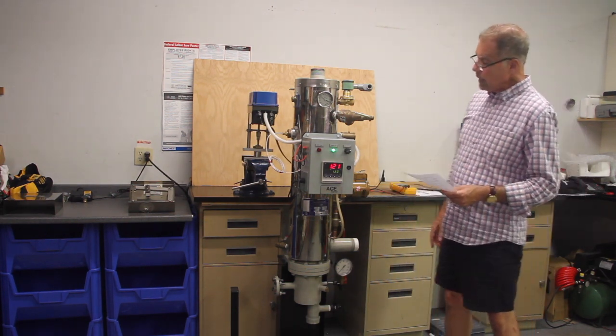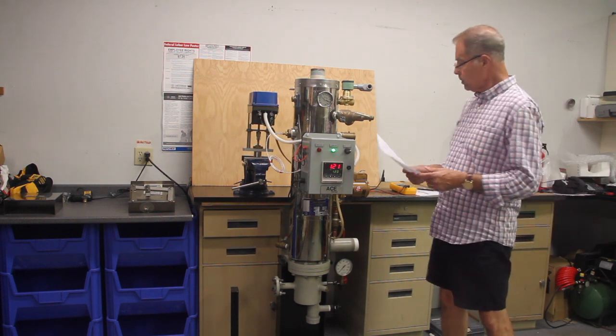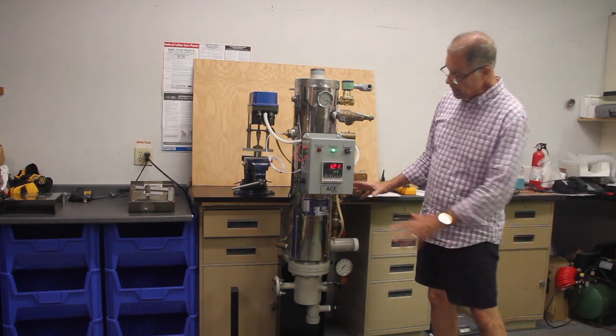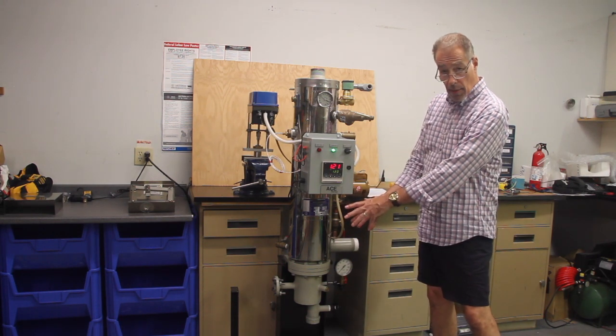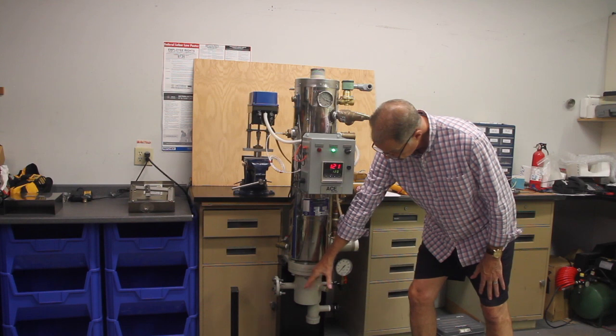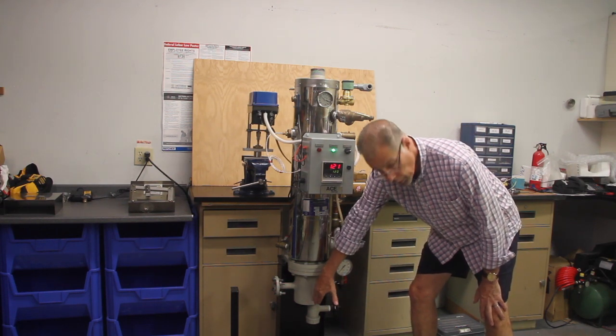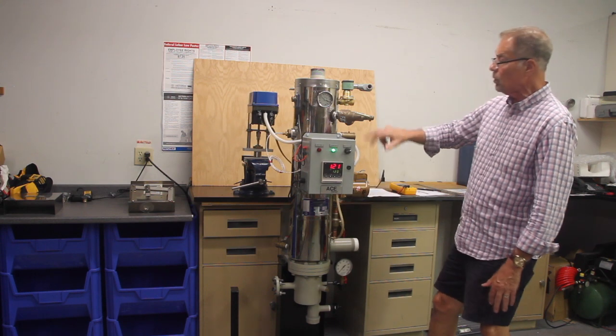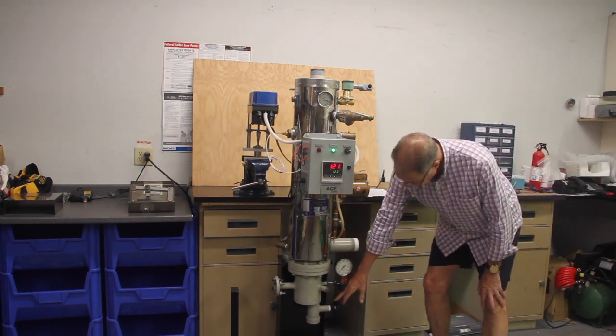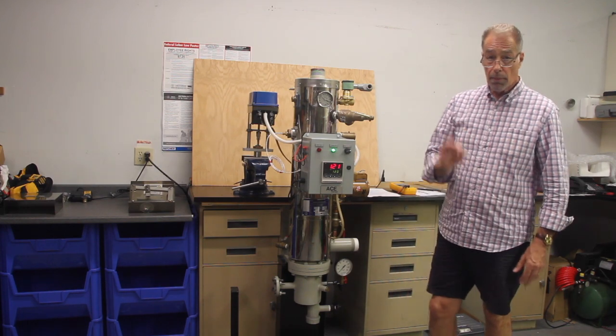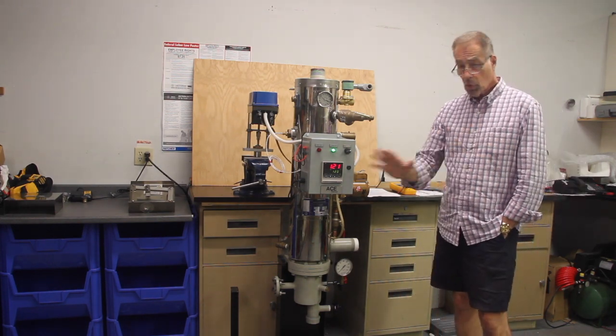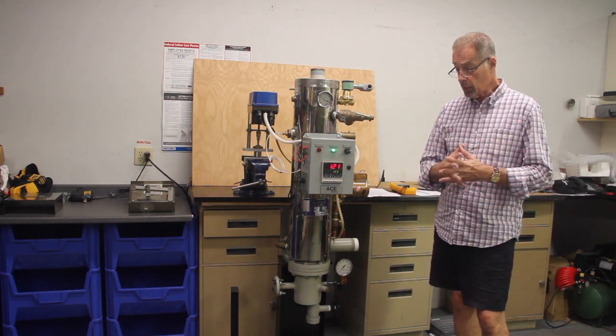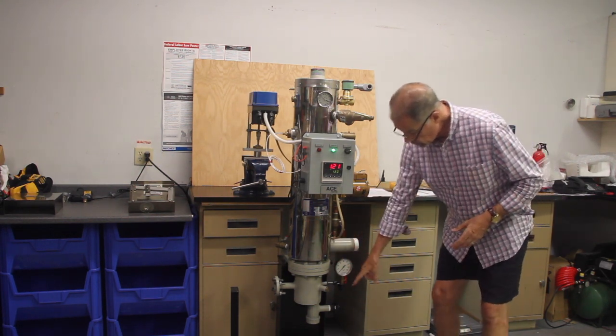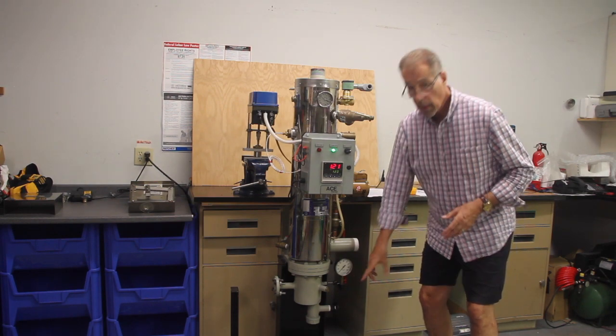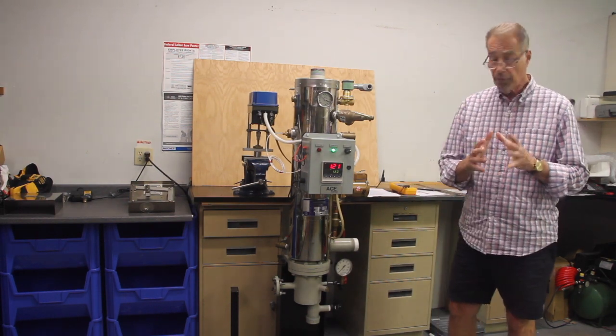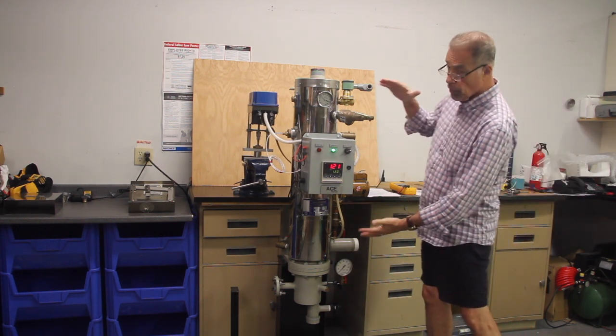The heater is a semi-instantaneous, and it's called that because the water is in the shell and the steam is in the tubing. So the primary media, the steam in this case, is going into this chest. There's a baffle here. It hits the baffle, goes up the tube bundle and back down, and it comes out of the heater as subcooled condensate. All the other steam on-demand water heaters deliver steam into the heater and deliver steam out of the heater. ACE didn't want to do it that way. ACE wanted to do it more efficiently, so we've added surface area.